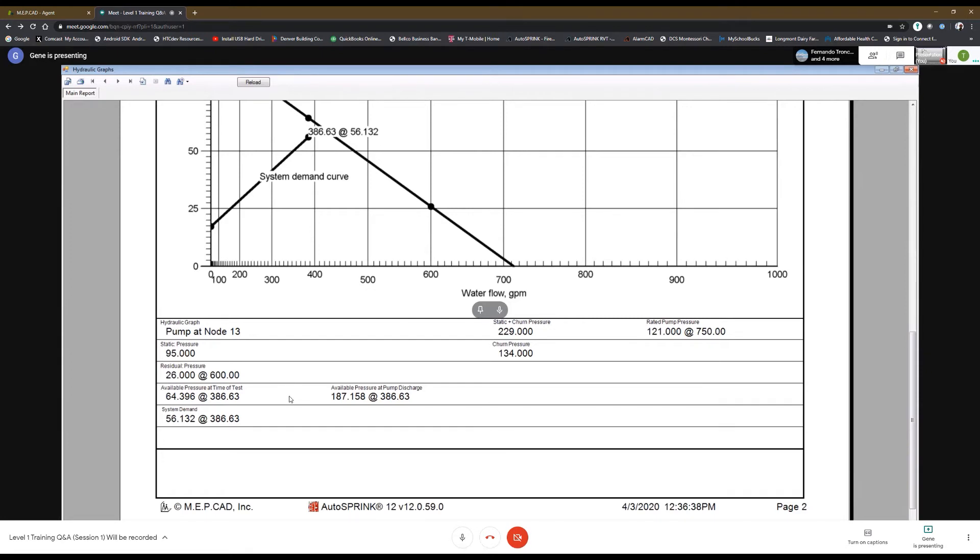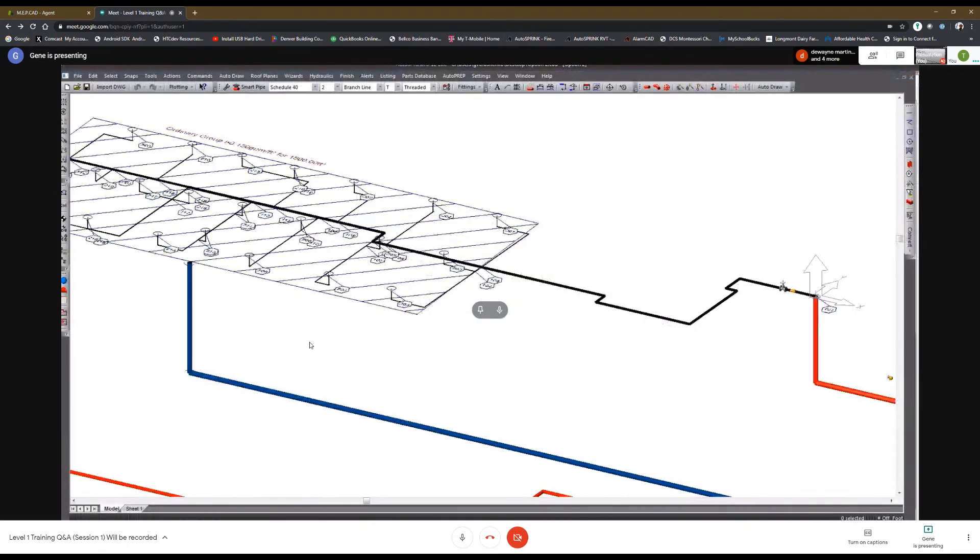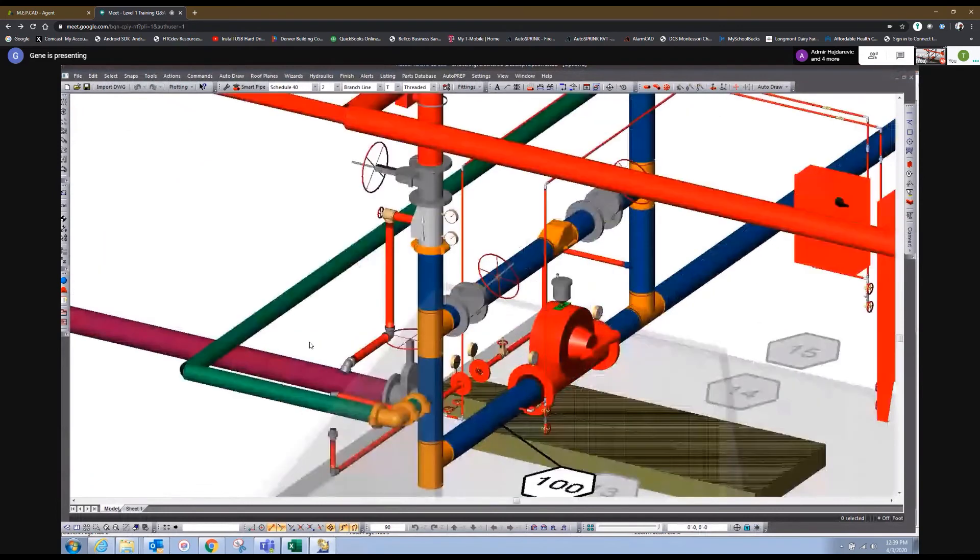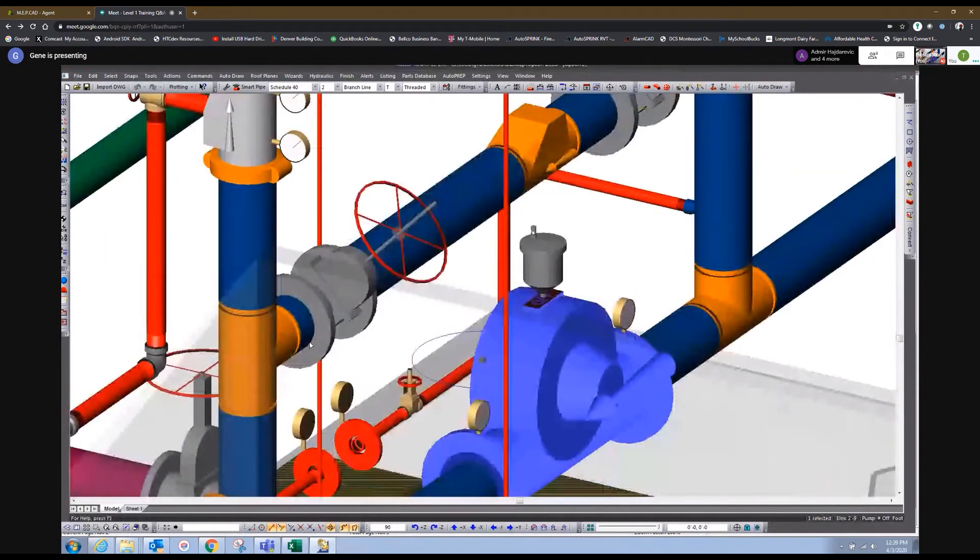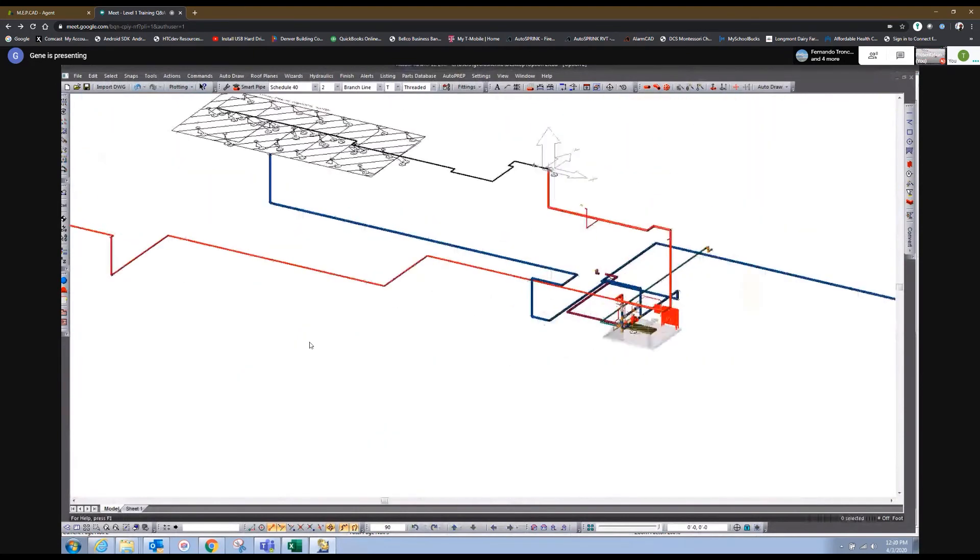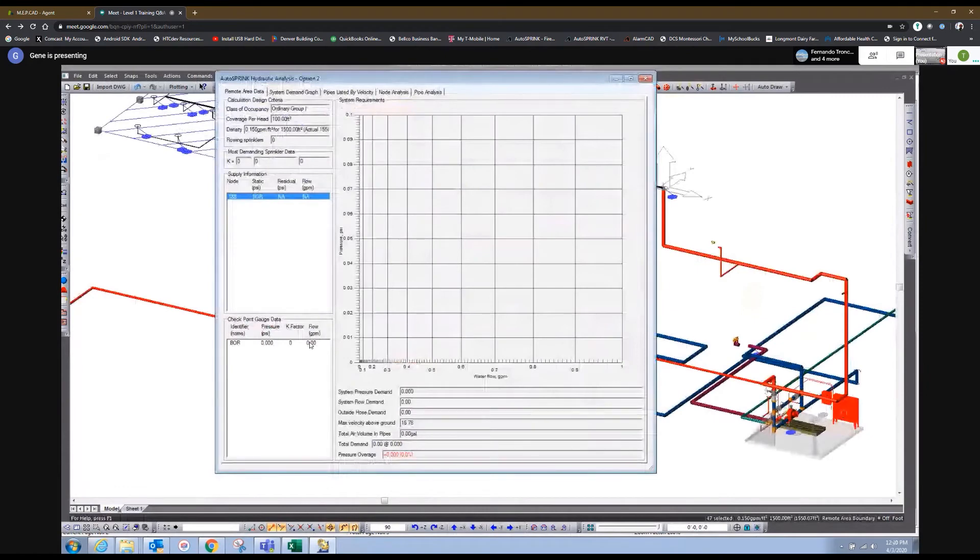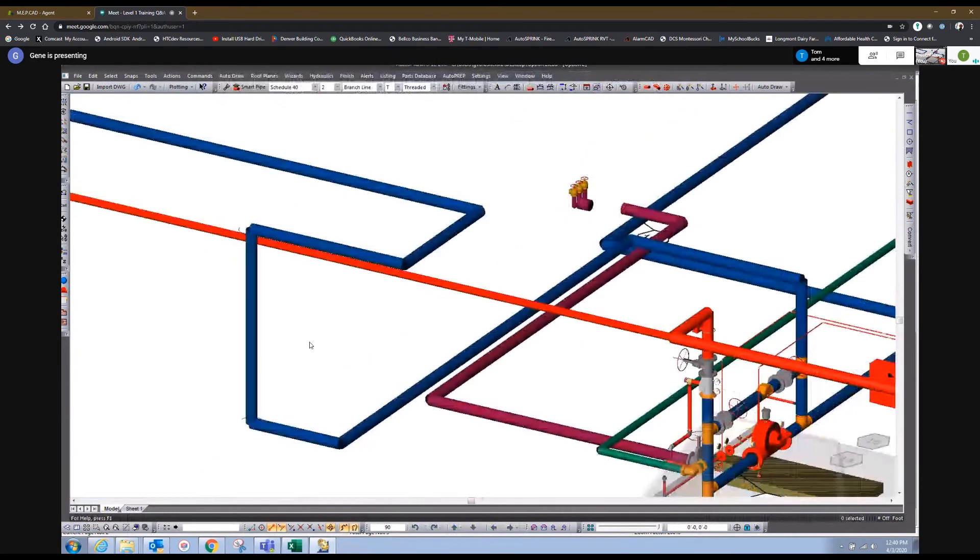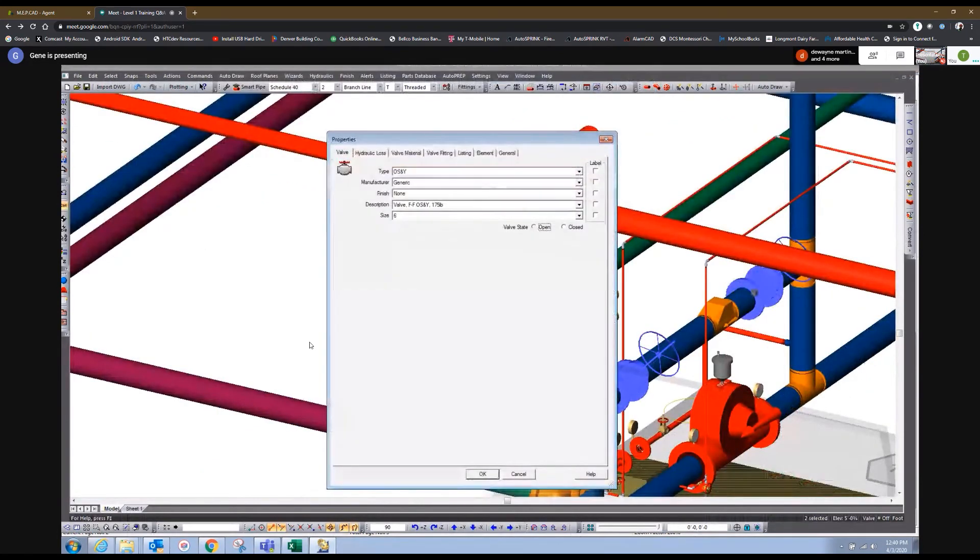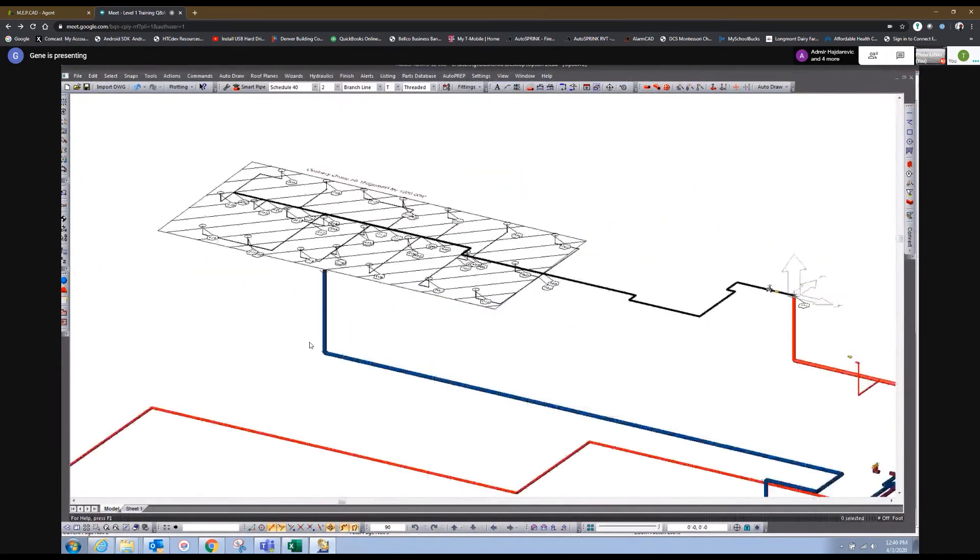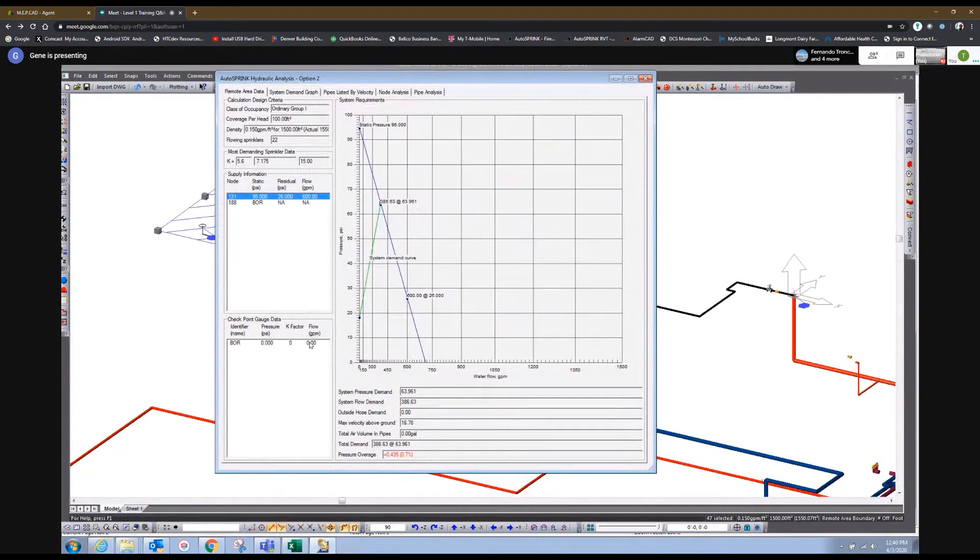If you were. I'm actually with Jensen Hughes, and we do have another version that the company uses, but this is my own. I got you. Understood. Because I can show you what it looks like on, so here's basic setup, right? Yes, sir. And then, if I shut off this pump, and I let it go through the bypass, which is always open. I have it open. Yes sir. Yeah, we, you might have a valve closed on the bypass. Yeah, one is closed. So, this is what I get. Now, 386 at 64, or 63.9. Yes sir. So, that's my demand.